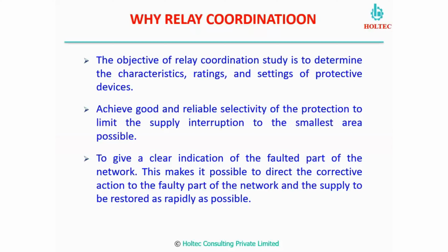So why relay coordination? I have already given you a brief of relay coordination in the previous slide. Basically, in relay coordination we define the characteristics of the relay, the rating of the equipment, the measuring equipment, and the protective relays, and we decide what settings we have to impose on those relays so that we can have effective protection. Then we can achieve good and reliable selectivity.